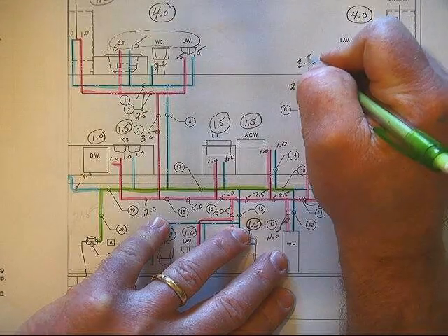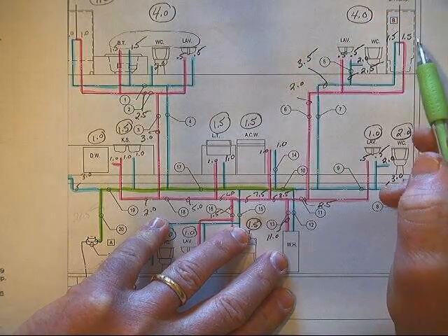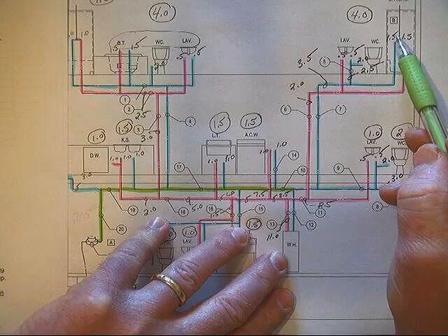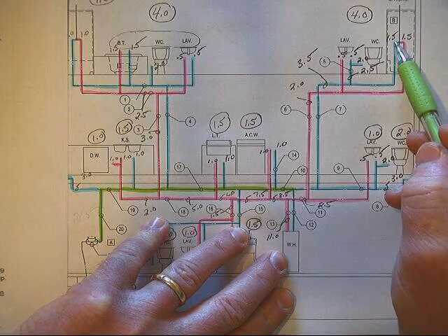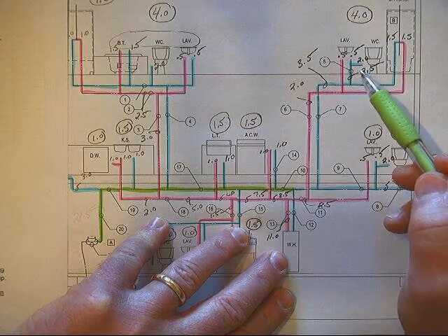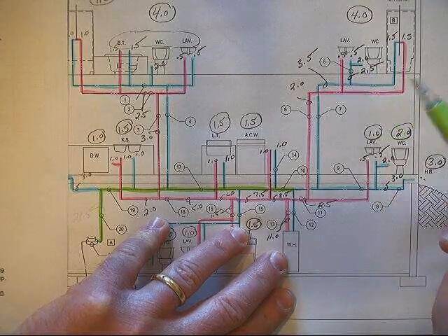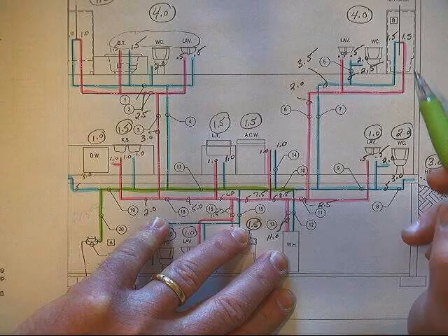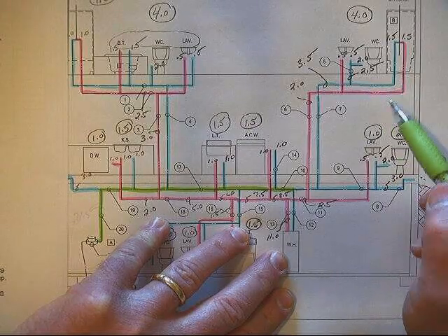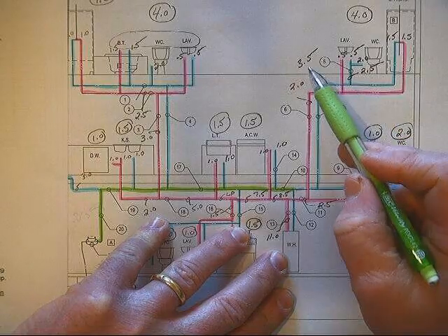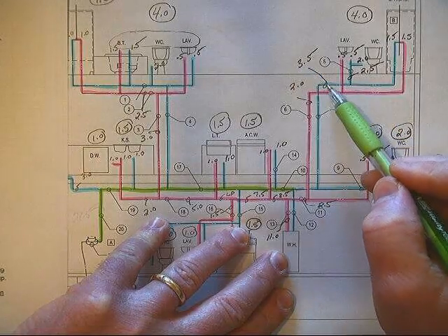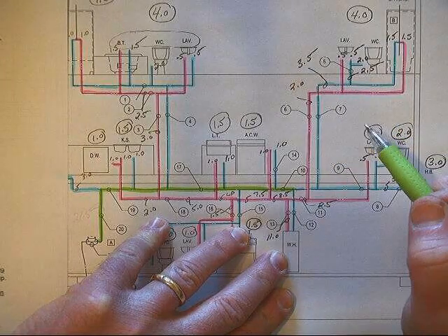So we'll write down 3.5, but what I want to point out is that if you added them up, mathematically speaking, of course, 1.5 plus 2.5 would have equaled 4, but due to the probability of simultaneous use, and according to our table, we are allowed to assign this piece of pipe 3.5.